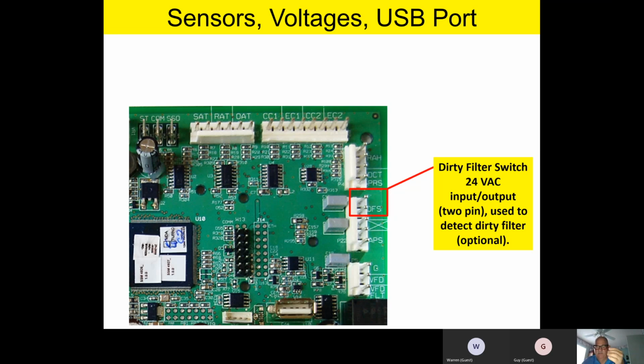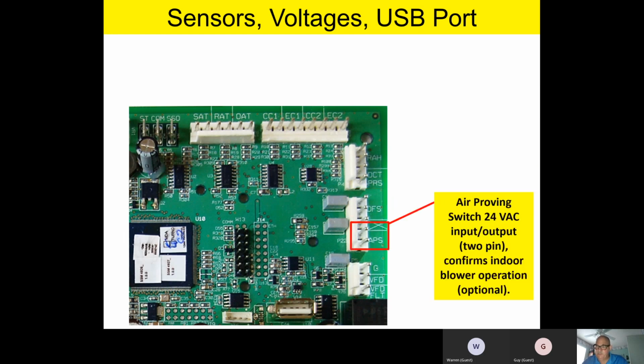You can literally just take your little diaphragm dirty filter switch, which is nothing more than just a little diaphragm switch that looks at pressure differential across the filter, and hook it right there on the board. And what it'll do, it'll monitor that pressure switch for you. And the board's smart enough that it'll actually give you a display on your user display if you have a problem. Or if you've got the MAP device, you can hook the MAP device in, take your smartphone, your smart device, your iPad, and you can go in and access all that information with your smartphone as well with the MAP device. As we move down the board, we have an air proving switch.